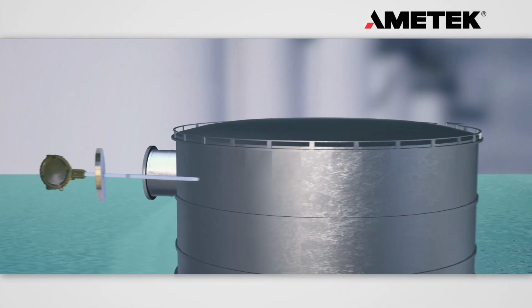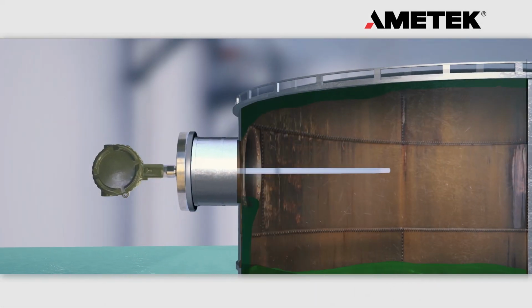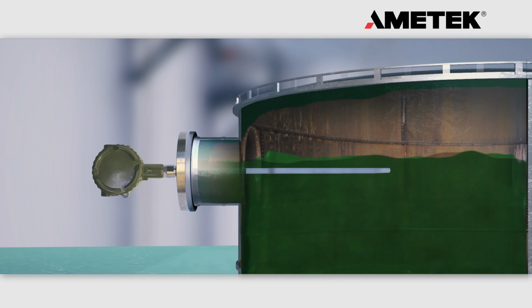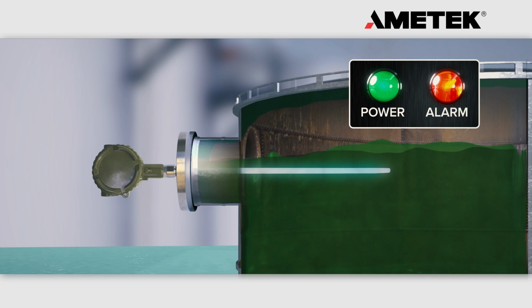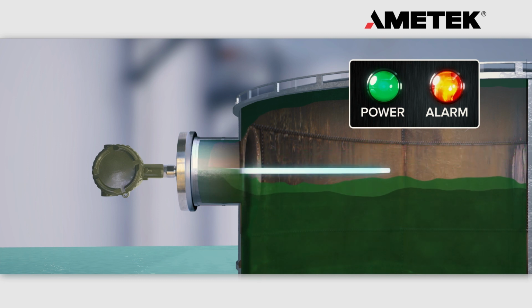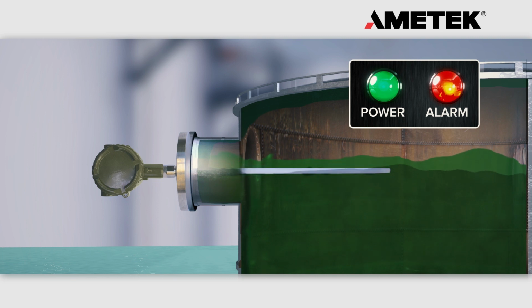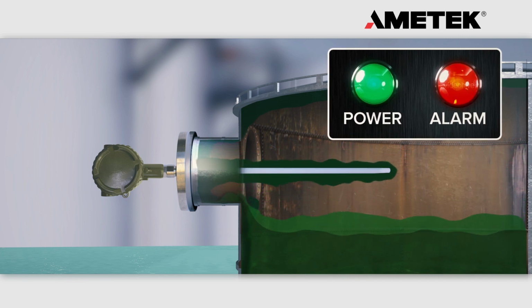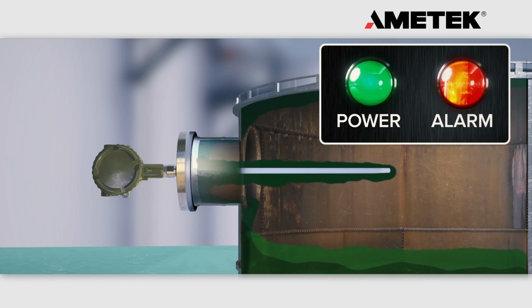When it comes to point level or on-off level measurement, process coatings can be a huge nuisance. The scenario is all too familiar. Tank fluid rises and makes contact with the probe, and an alarm is signaled as it should. The problem arises when the process media drops back down and leaves a coating or film on the probe, leaving the probe in an alarm state. An obvious false alarm.